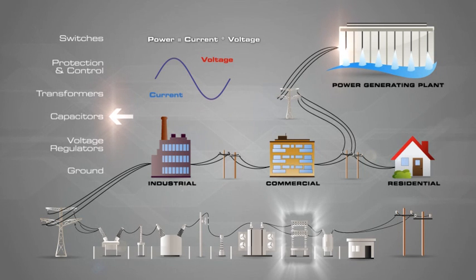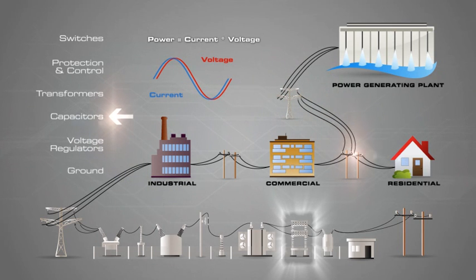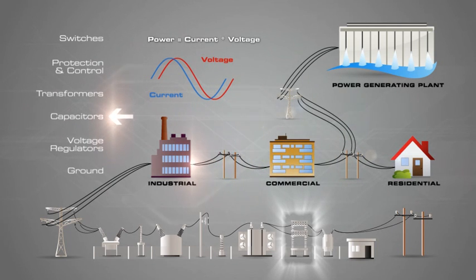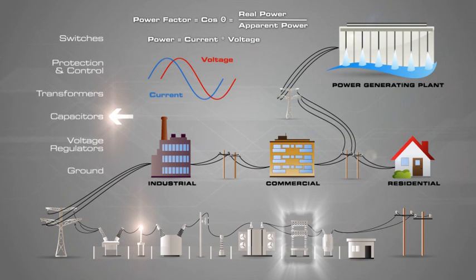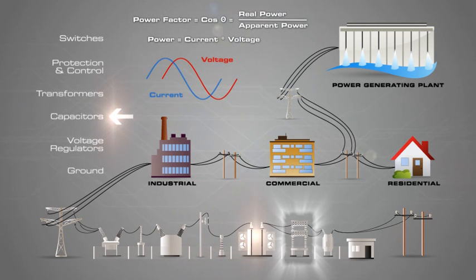Power is the product of current times voltage. As the power leaves a power generation plant, the voltage and current are in phase. As power is transmitted through the transmission and distribution grid to the loads, there are significant losses of power due to phase shift. Power factor is the cosine of the phase shift between voltage and current, or the dividend of real power divided by apparent power. Capacitor banks are located throughout the grid to correct for these phase shifts and improve the efficiency of the grid.